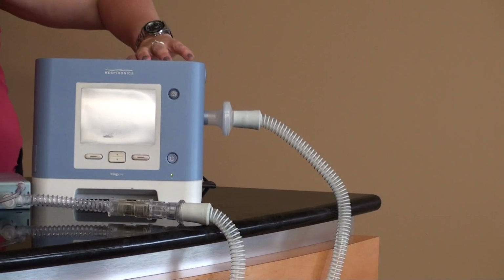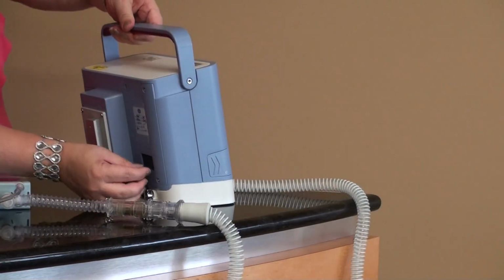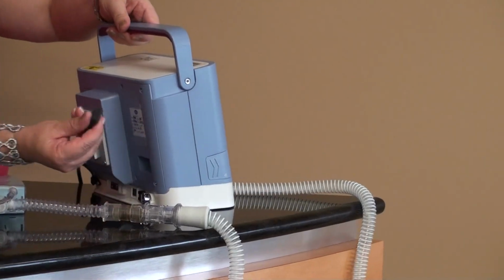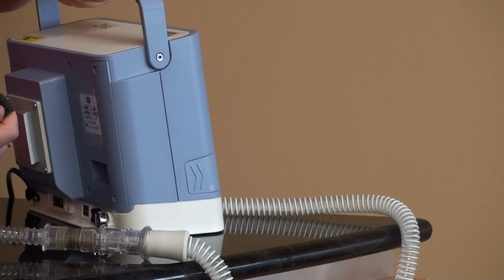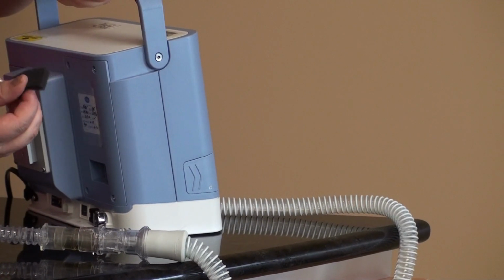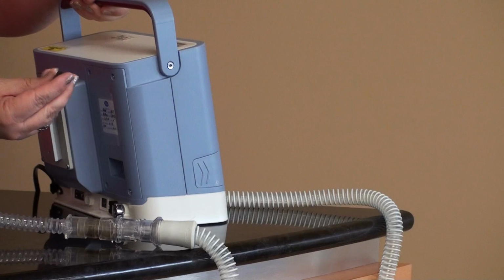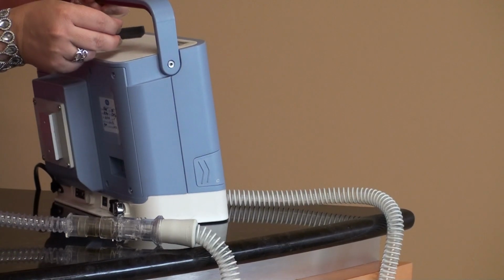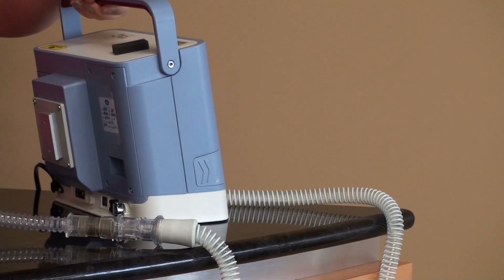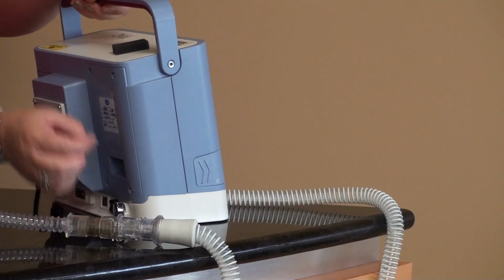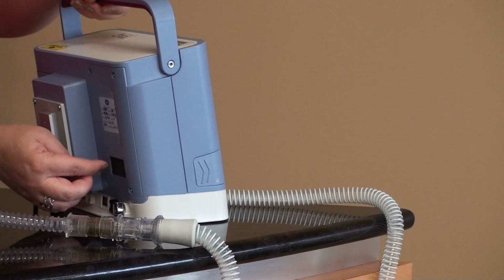The other thing in the back, one more thing that I want to point out, is your gray foam filter here. Just like your other ventilators that you probably used, this needs to be washed out. Check it every shift. If it's dusty, dirty, wash it out with water, no soap in it. Let it air dry. Take your extra one out of the drawer and put it in place of here. So then you always have a dry one that goes in.